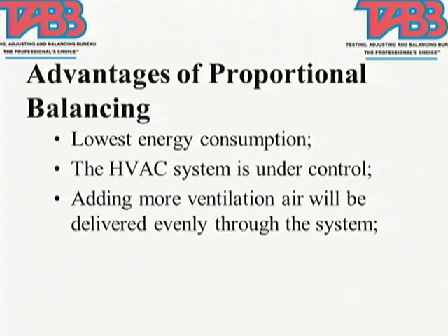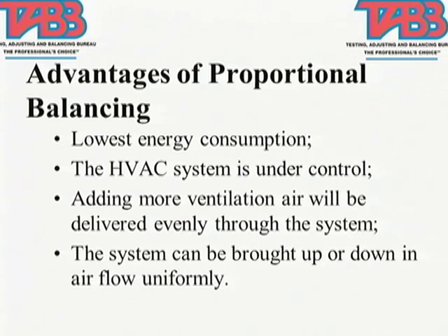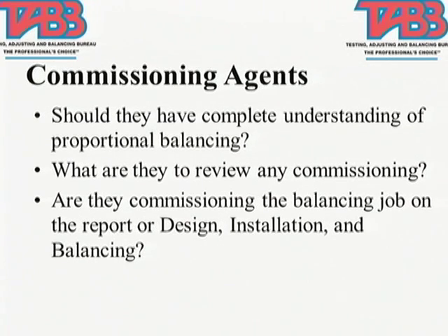More ventilation air will be delivered through the entire system when we're talking about bringing fresh air into a building. The system can be brought up or down. Now this is where we have an issue, and I have seen it happen over and over again, where they bring in commissioning people to commission the hydronic balancing or the air balancing. The commissioning agent comes in and says, I have a checklist, and my checklist says that that needs to be at no less than minus 10%, and that one's at minus 30%. You need to make that one right. The only thing the balancer can do is go and put more restriction on other dampers, throttle those dampers down. As soon as he starts throttling other dampers down, the static pressure starts going up in the duct system. Static pressure goes up, velocity pressure goes down, we have less flow. So we have a higher static and less flow.